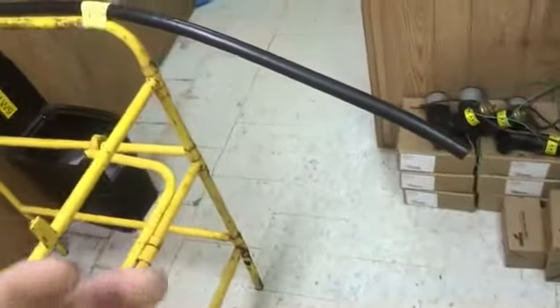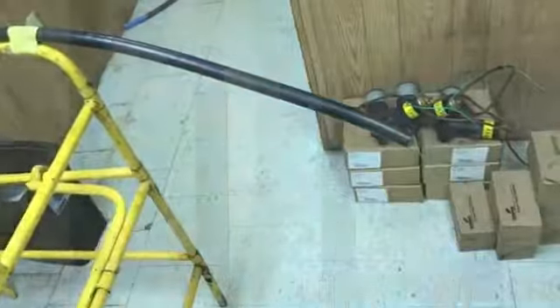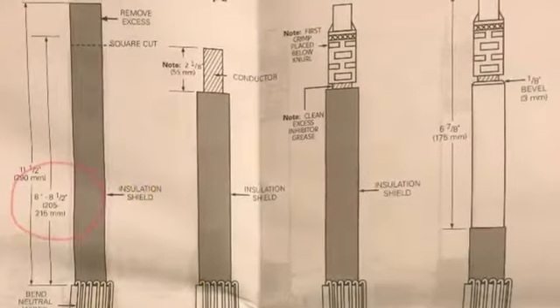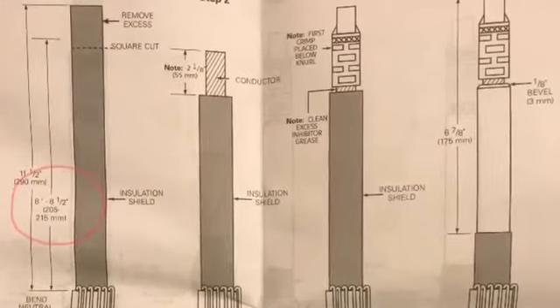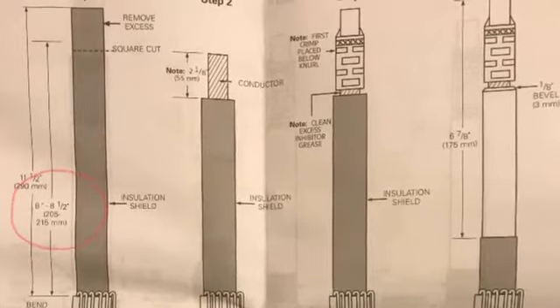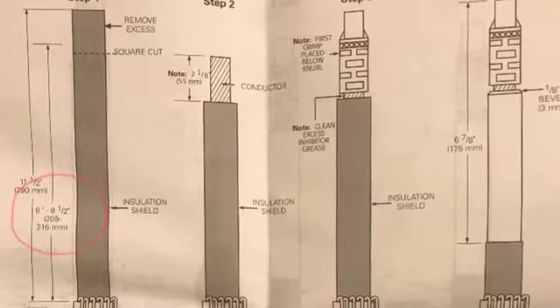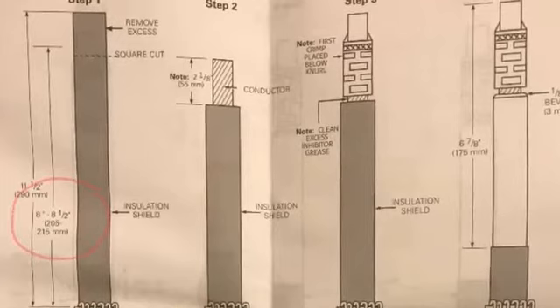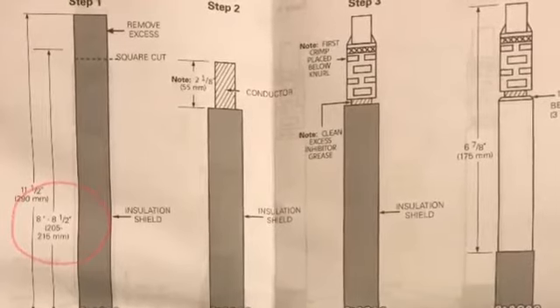So just something to keep in mind, the difference between a compact cable and a compressed cable. Our first step is determining what our jacket cutback length is going to be. This particular set of instructions is for a jacketed concentric neutral cable.